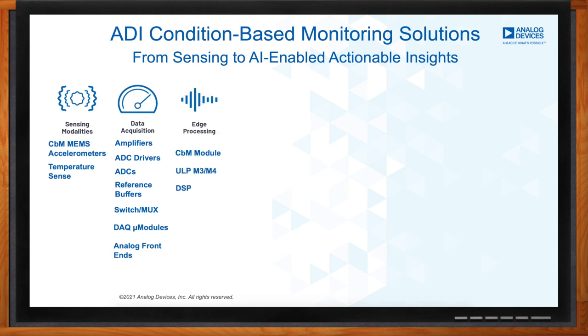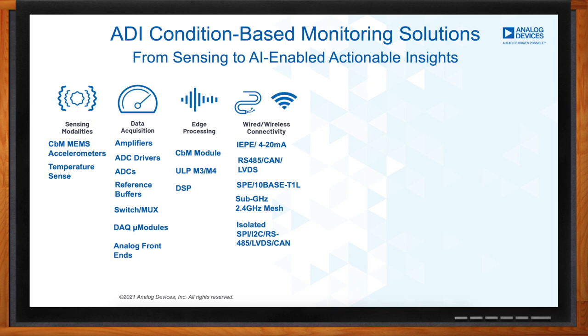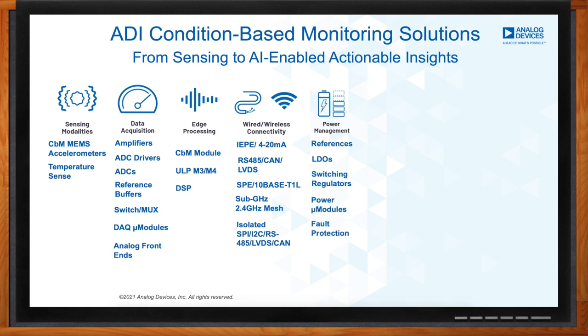Once we have asset health information in the digital domain, we deploy edge processing to create asset health data that we then need to communicate across the plant. There is a wide range of wired and wireless connectivity options. On the wired side, we have IEPE, 4 to 20 milliamp, RS-485, CAN, LVDS, and new single-pair Ethernet technologies like 10Base-T1L that can provide both power and data on a single twisted-pair cable. We also have isolated transceivers. On the wireless side, we have sub-gigahertz and 2.4 GHz smart mesh technology. Analog Devices also has a broad power management portfolio covering power regulation, protection, and references to power all these components.